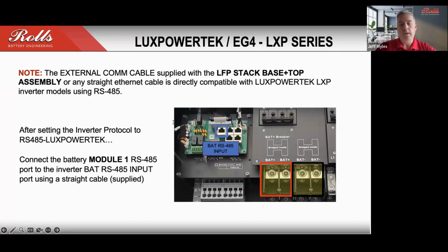So what we've done is built essentially a step-by-step guide, which will walk you through the programming of that particular equipment. One thing I will note is that as they apply firmware updates to the equipment, it's possible that some of the menu may change. In those cases, we will make every attempt to update those, but it's possible that these could become outdated. In that case, we would welcome your feedback and we will certainly address that. We do work very closely with the inverter manufacturers to get that documentation and to complete testing. So in most cases, they're reporting that to us anyway.